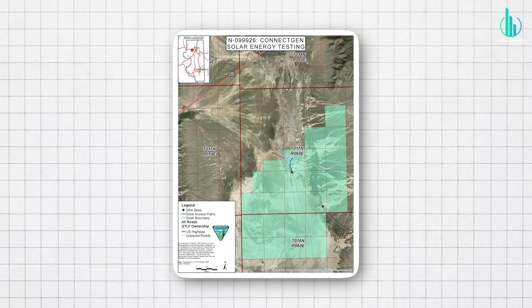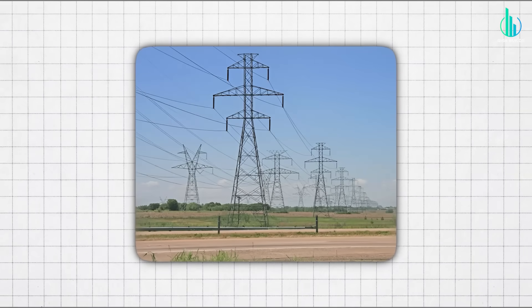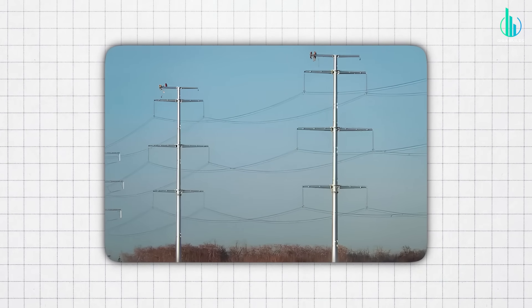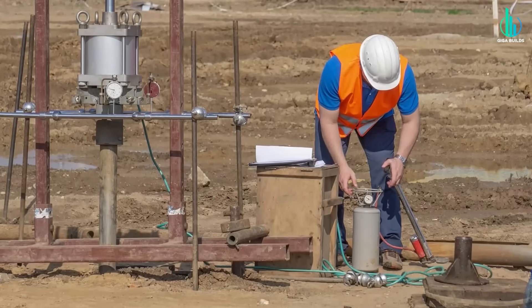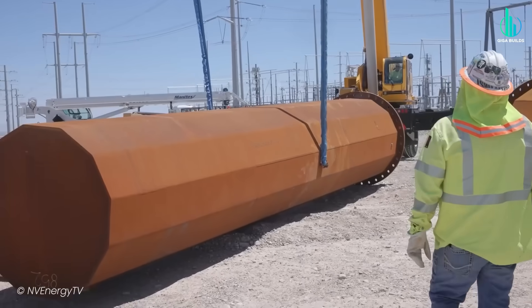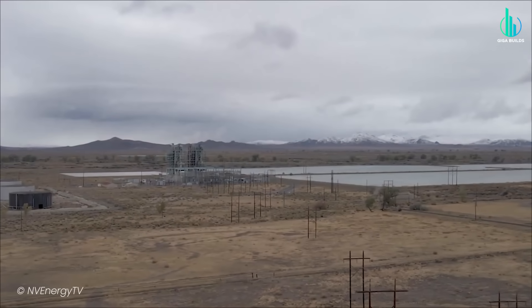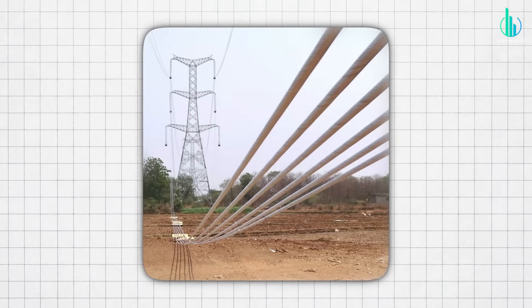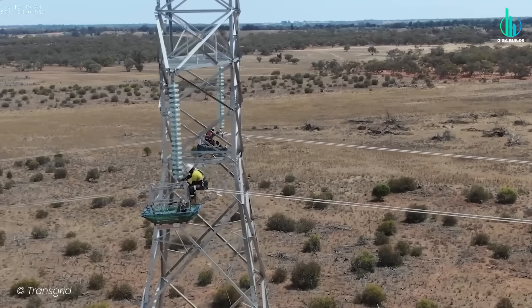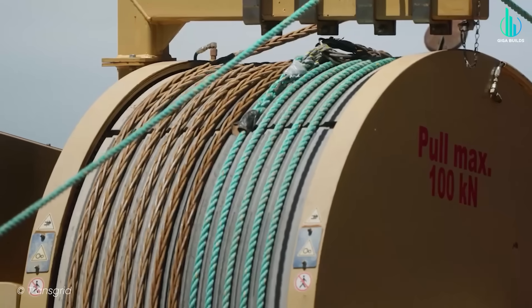These lines don't just get built — they're discovered, like a route across mountains and deserts that keeps risk low, environmental impact lower, and reliability high. The towers are a mix of lattice steel and tubular monopoles, chosen based on terrain and visual impact. Every step is bespoke: soil testing for corrosivity and stability, foundations ranging from spread footings in solid ground to deep caissons where the geology gets sketchy, and access roads carved out to reach tower sites that are often nowhere near civilization. Then there's stringing conductors — those thick cables that carry the juice — with tensioners, winches, and helicopters in the roughest spots, teams watching sag and tension like hawks. At this scale, gravity is not your friend.